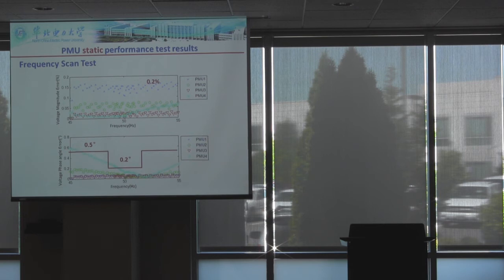But you know, we did the PMU dynamic test in our lab. Here I show some results. This work was done last year, and here are the four PMU manufacturers' products. The first one is about the static test. When the frequency changes from 45 Hertz to 55 Hertz, we can see this is the voltage magnitude error. And this is the Chinese specification: the error should be lower than 0.2%. And we can see that the static performance is really good for PMU.